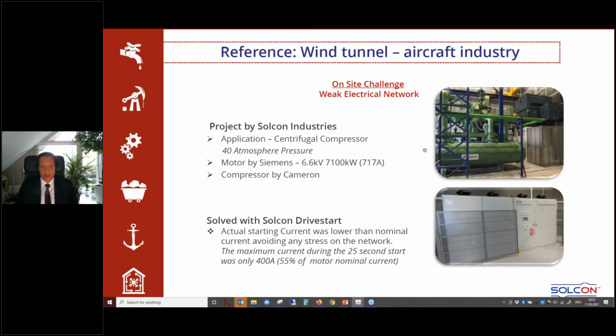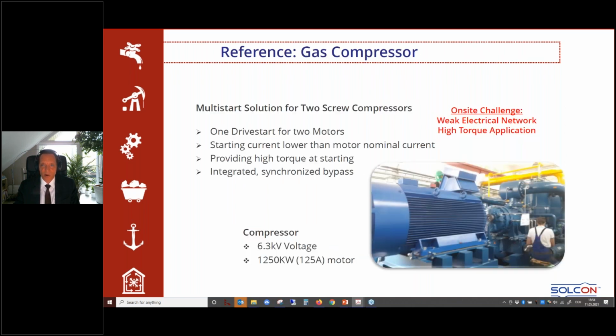Some examples of what we have done with drive start. Here it was a wind tunnel by Solcon Industries. It was with a centrifugal compressor with 40 atmosphere pressure. Motor was from Siemens, 7.1 megawatt, 6.6 kV. Compressor was from Cameron. The motivation was that we needed to avoid any stress on the network, and maximum current during the 25 second start was 400 amps, which is only 55% of nominal current of the motor.